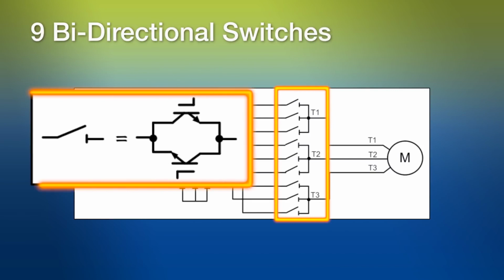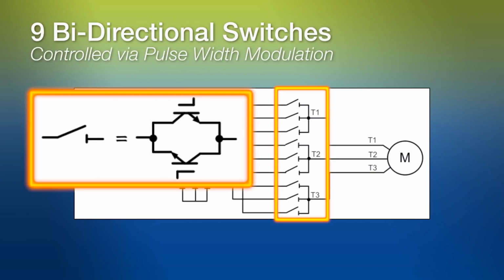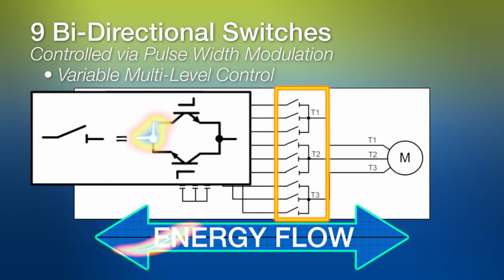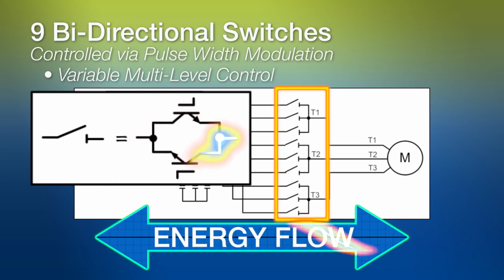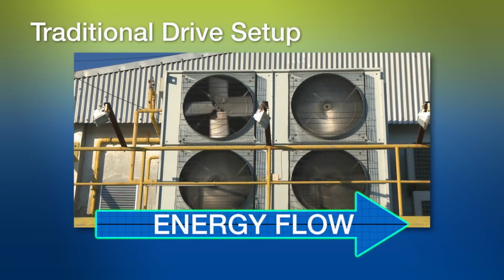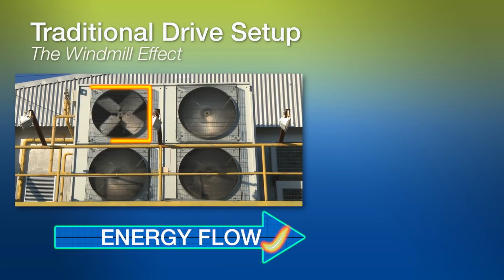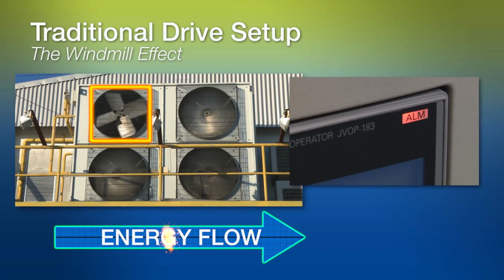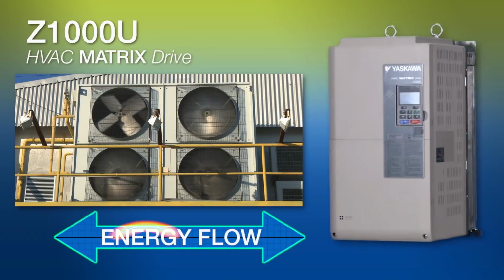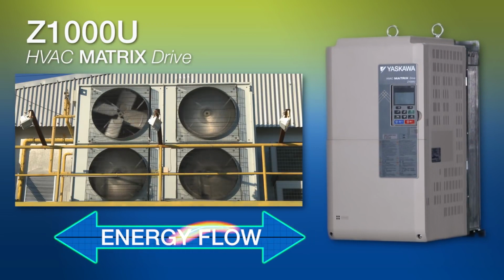Nine bidirectional switches are controlled by pulse width modulation, or PWM, with variable multi-level control. Power can flow in both directions through the switches, meaning the unit is fully regenerative. For example, when trying to slow down the motor speed quickly or correct the direction of a motor that is already spinning, a windmill effect can cause traditional drives to trip out on various faults due to excessive DC bus voltage and/or higher starting current. The Z1000U eliminates those faults and actually applies that previously wasted energy back to the supply. This makes the Z1000U perfect for catching freewheeling motors regardless of the direction.